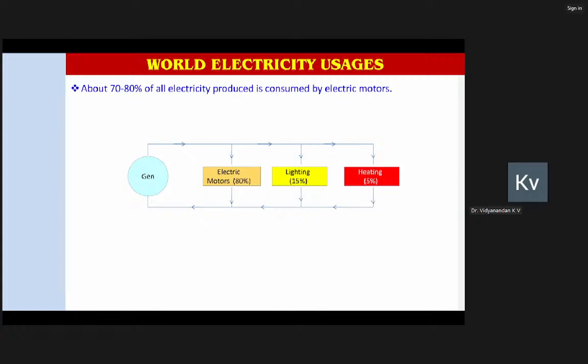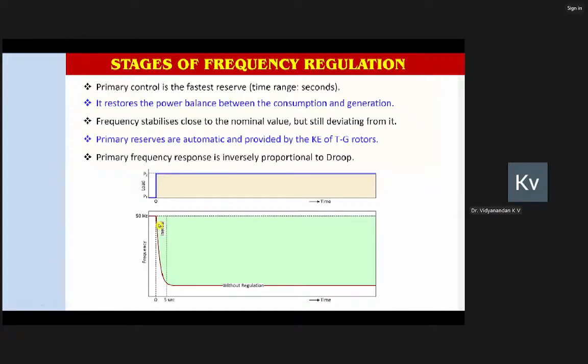Whenever the frequency varies, the governor will come into action, and through the governor action, the control valve will open, more steam will be admitted, and it will arrest the fall in speed. So the second curve represents the primary governor action, which stops the fall in speed, and finally speed or frequency is stabilized.